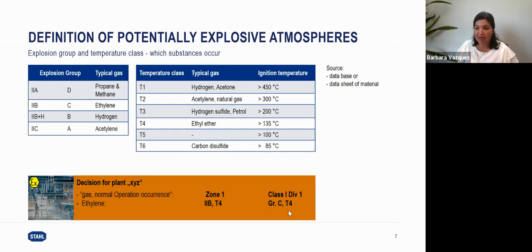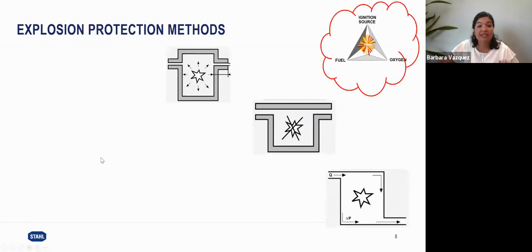Okay, so now we have our process. We have defined the hazardous area that we're going to be working with, and we're going to install electronics in it, right? Instrumentation, because that's what we're talking about here today. Instrumentation like pressure transmitters, temperature sensors, level sensors, solenoids, proximity sensors, right? Beacons, horns, pilot lights. So how do we protect these electronics to make sure we don't get that spark, we don't get that heat that can react with the explosive atmosphere?